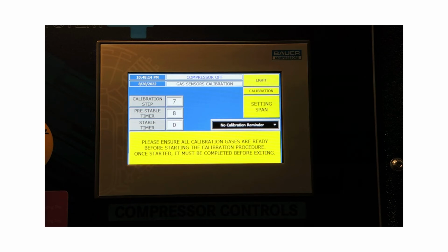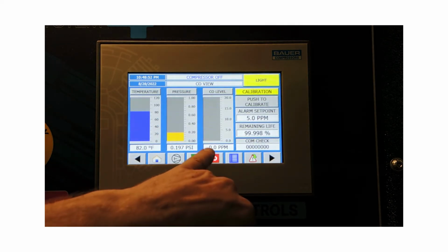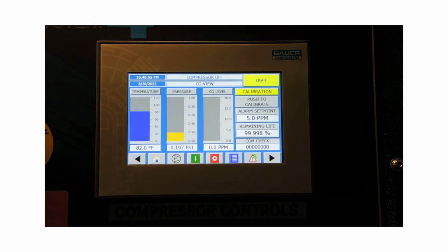The 20 part per million span setting is almost done with the pre-stable timer, and then it'll go into the stable timer. Just pointing out that the customer here has requested that there's no calibration reminder set up, but you can set that to remind you at certain periods, 90 days, 30 days, whatever is required by your department. Once it gets done with the stable timer, it'll say calibration complete. One of the things I like to do is hit that button, and at this point I should see the 0 part jump up. I still have the pressure, so this is still the 20 part.